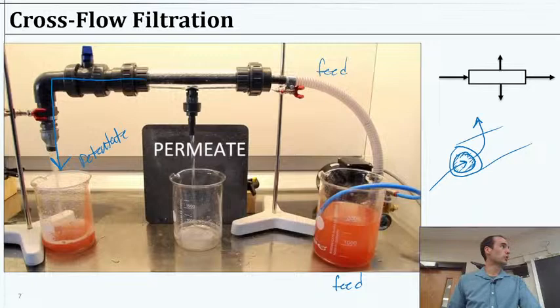And you'll notice up here, there's some sort of a valve that is very likely adjusted to apply pressure, to force water through a small gap so that there is pressure exerted on the water to make its way outside of the membrane, right? So we will restrict the flow through the retentate line in order to cause that pressure, because otherwise it would just take the path of least resistance and go straight through.